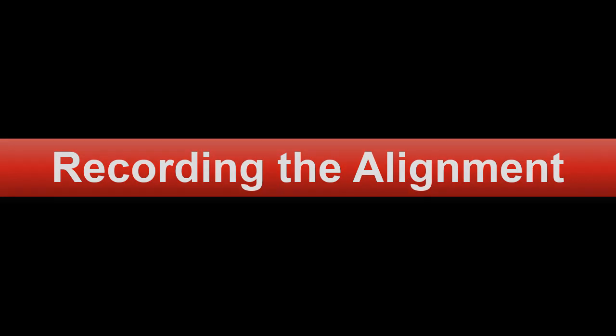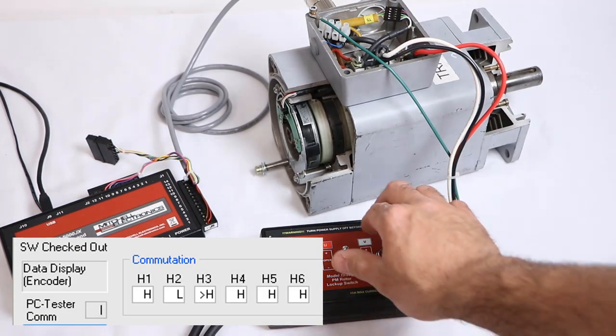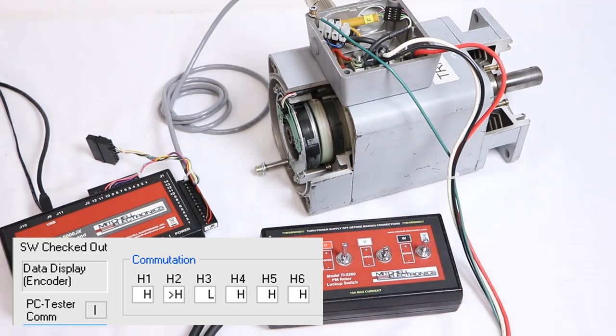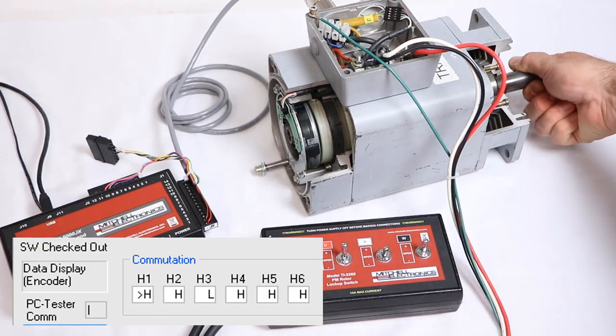If the feedback is testing well, then it's time to check the alignment. Lock the motor with the manufacturer-specific lockup pattern, then wiggle the shaft, and look for a toggling pulse, seen here.